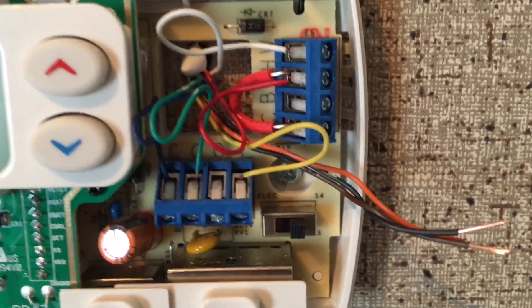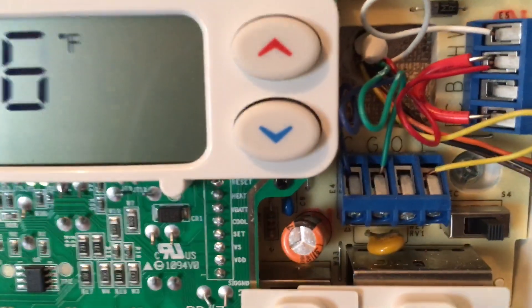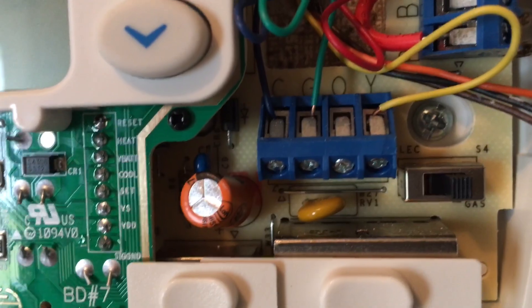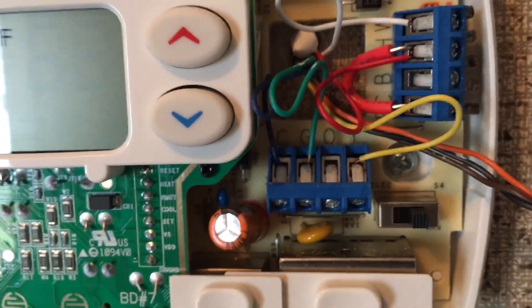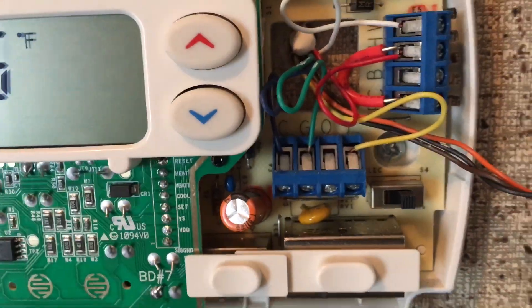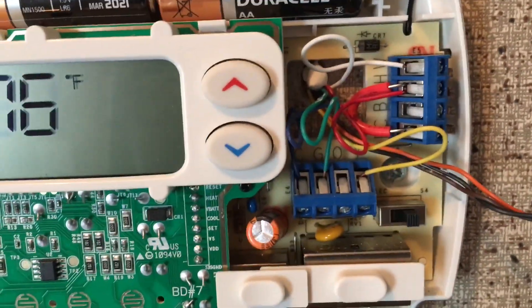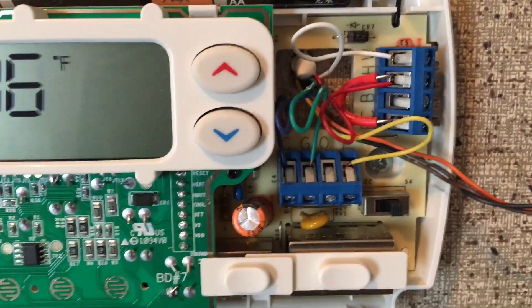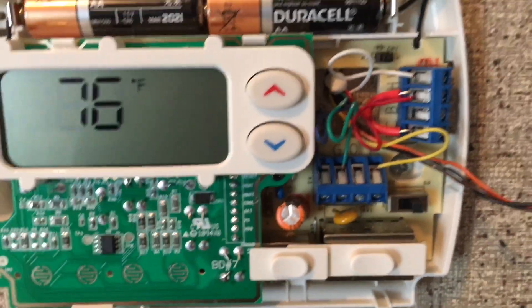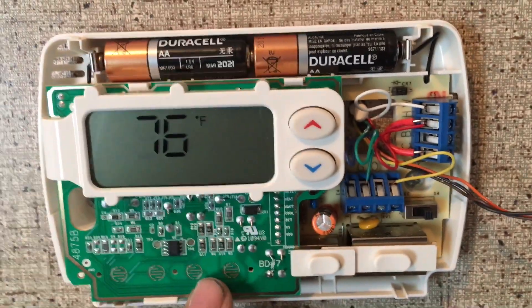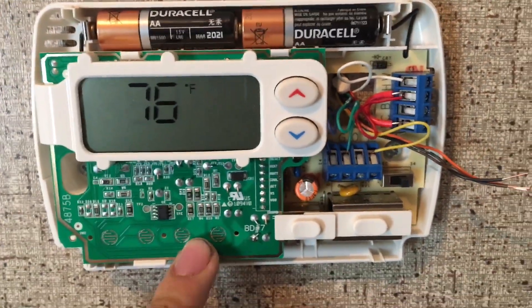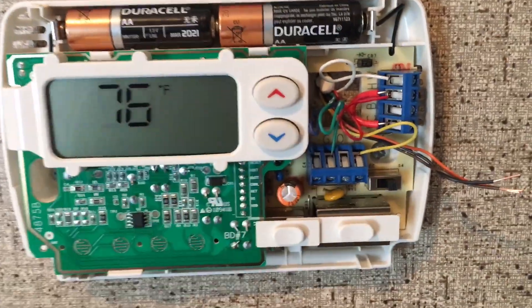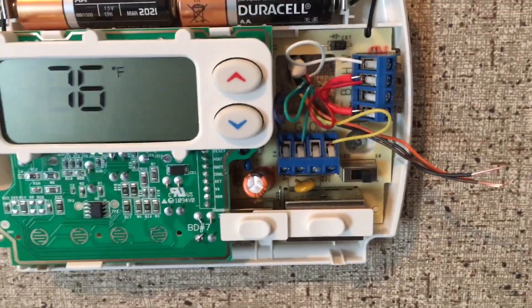Okay, the blue wire that's also hooked up here, that is a common wire, which is the other side of the 24 volts, which will let this thermostat power itself without having to use the batteries because it has both sides.